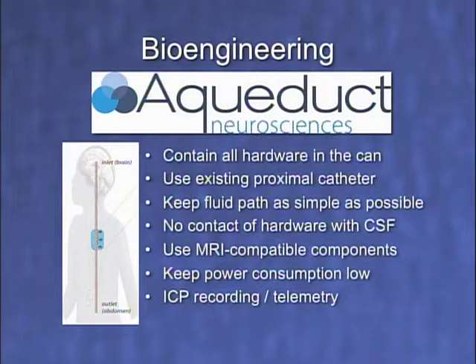Through those efforts, we've developed a new shunt valve that we think is going to have great benefits on several levels. One is reduced failure rates, both at the valve and at the proximal catheter. So we have some technology we think will address that. It also hits on several important things. It's MRI compatible. Right now we do get MRIs on kids to avoid CAT scan radiation, but you have to reset the valve, and the valves are magnetic, and so we have valves that break because they're exposed to the magnetic field. So if you could have a totally MRI-safe valve, that's a huge thing. We're incorporating that into the design.